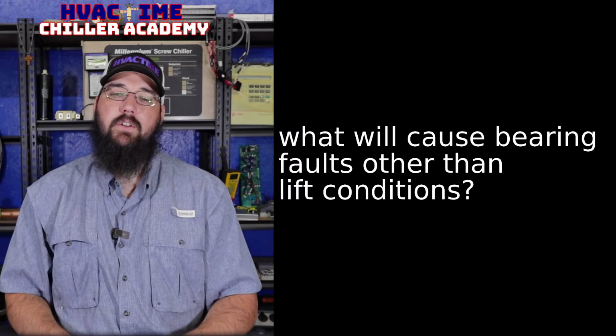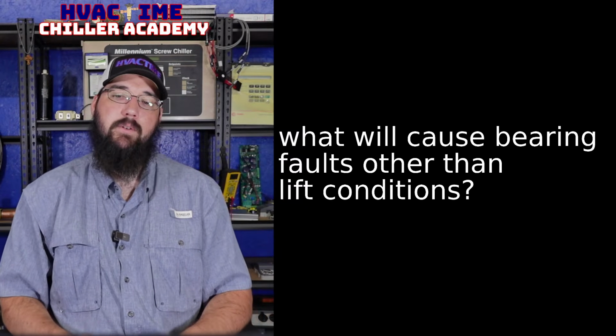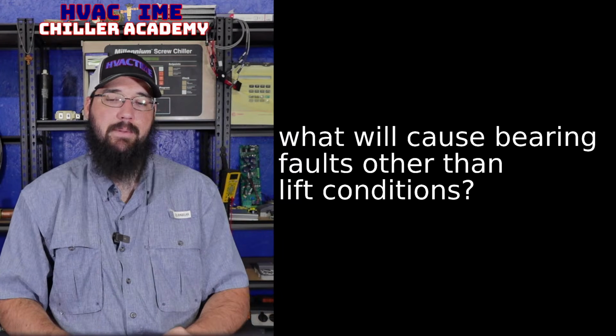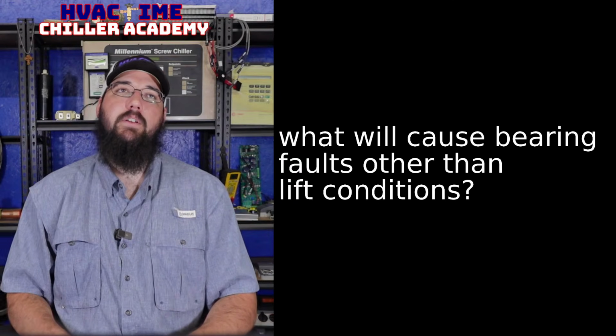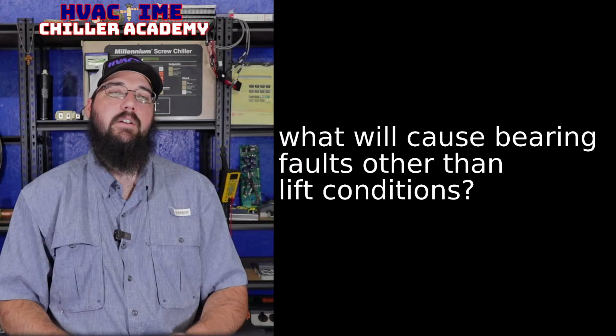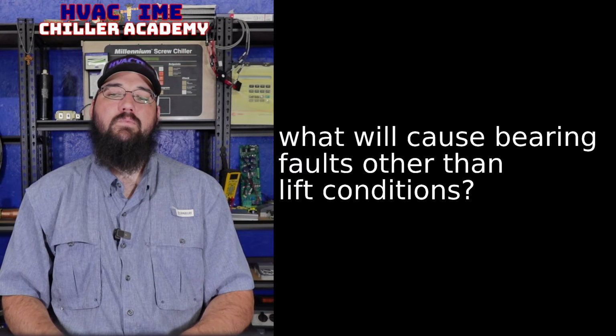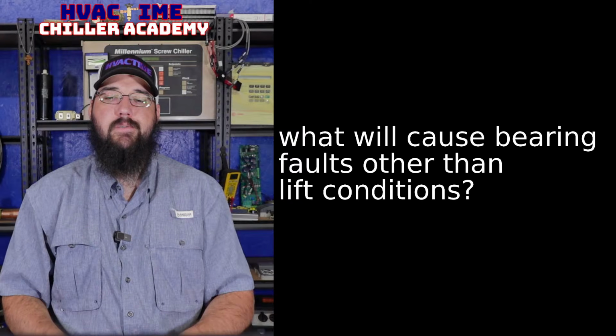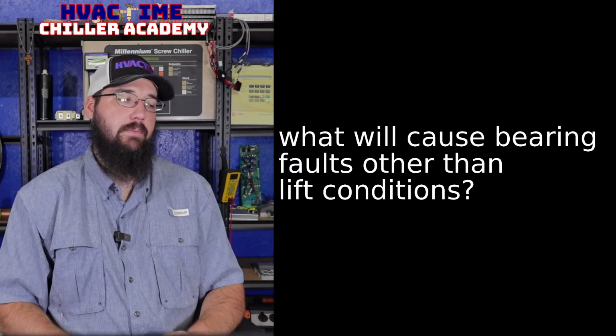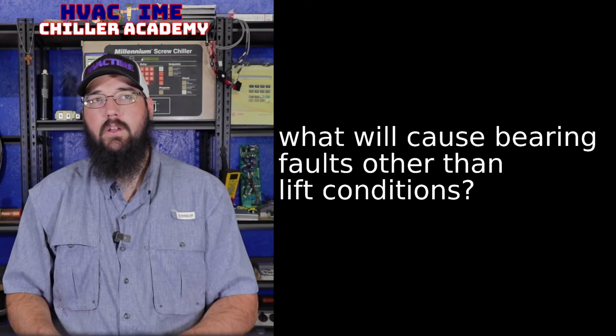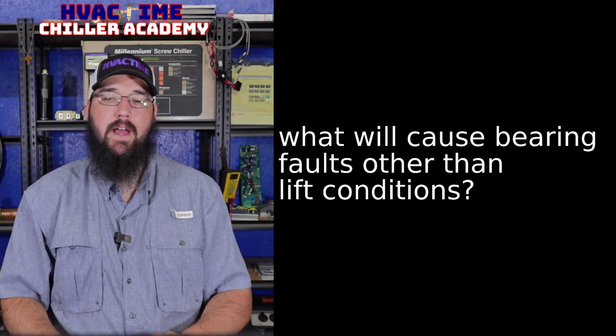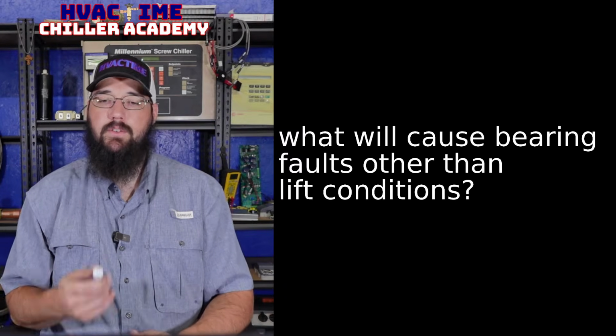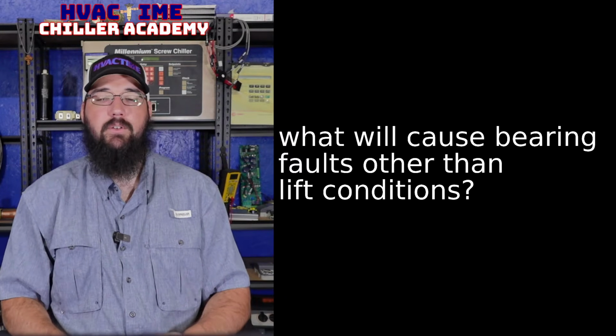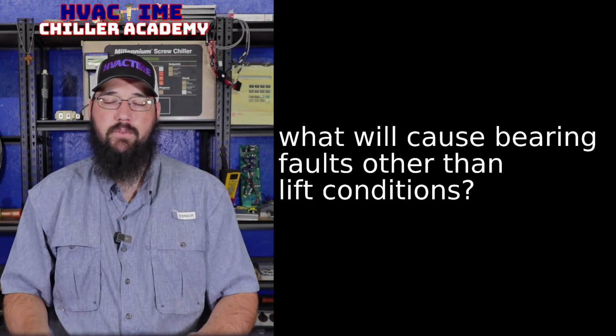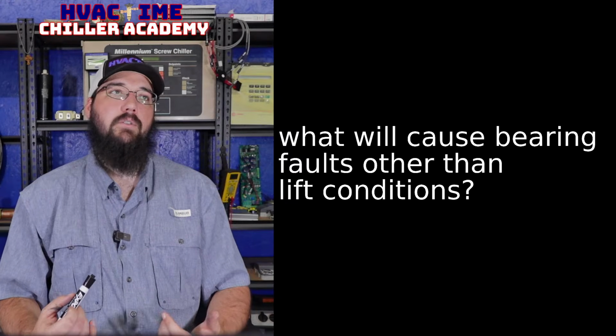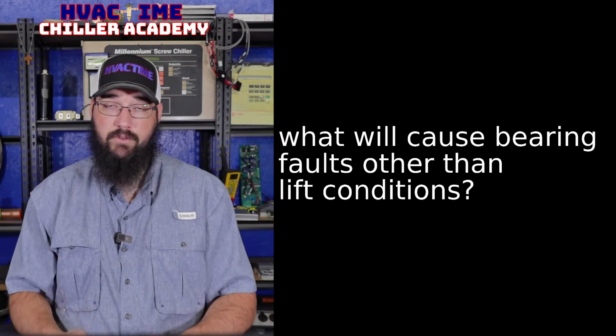I mean, if it's able to start up and run long enough that you can walk away from it and you're not seeing it happen live in front of you, then you probably are looking at some kind of lift concern, or you're running a wet suction, something like that, after you leave. So Tom and Jason have really solid points: if it's not tripping with it in front of you, you're able to verify lift or the refrigerant level in the evaporator, because you can monitor your suction superheat on this.